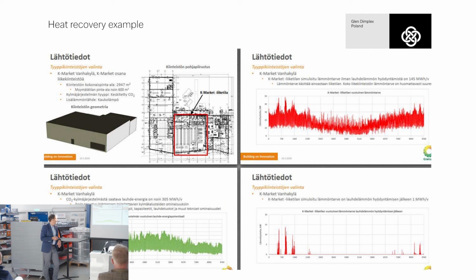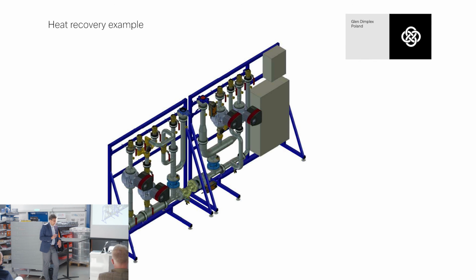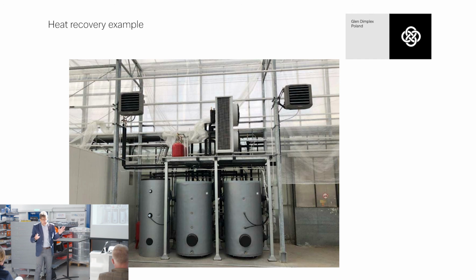Of course, we have some other examples, some other measurements available, but it's only the main message that it could be a very effective system. Coming back to the parts of the system, as I mentioned, we can design and provide you as contractors or executive company with such pre-mounted parts of the system. We can build in the circulation pump. Everything is in the frame, easy for transport, with easy connections, flange connections. Also with the electrical cabinet, with the controller, and with other necessary parts from the electrical side. It looks very compact.